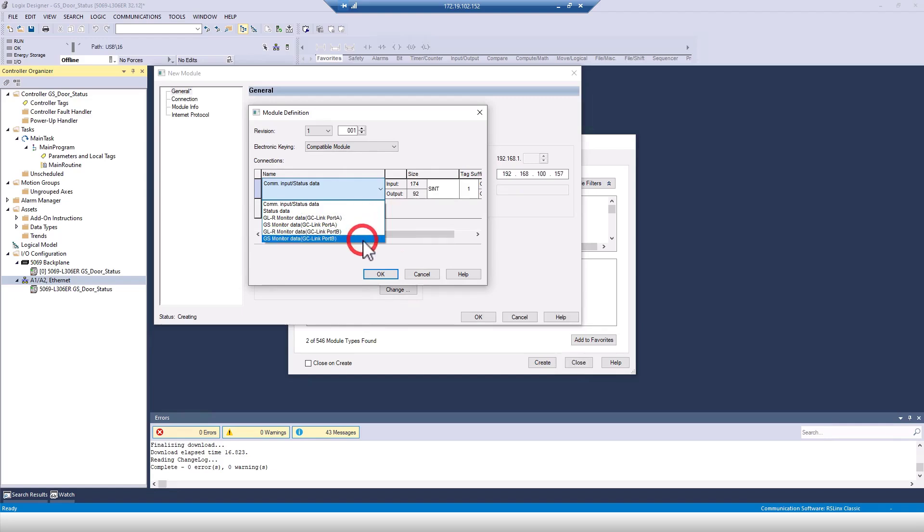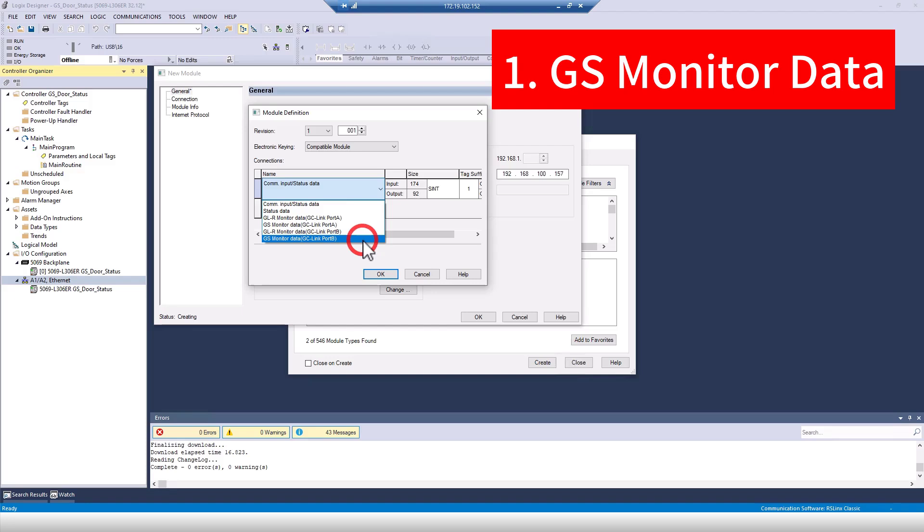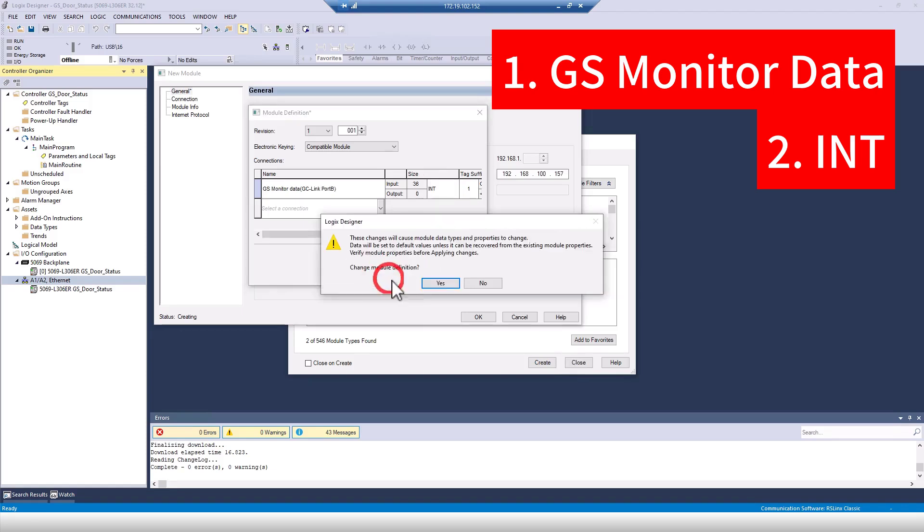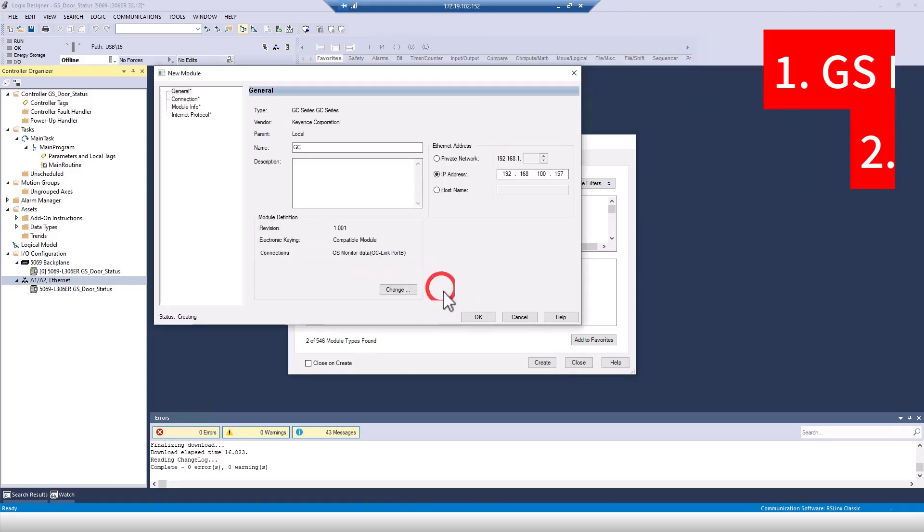Instead of communication input slash status data, we'll want to use a GS monitor for the correct port the interlocks are connected to. An important note here, make sure the connection type is set to integer or int, or else the AOI won't work later.